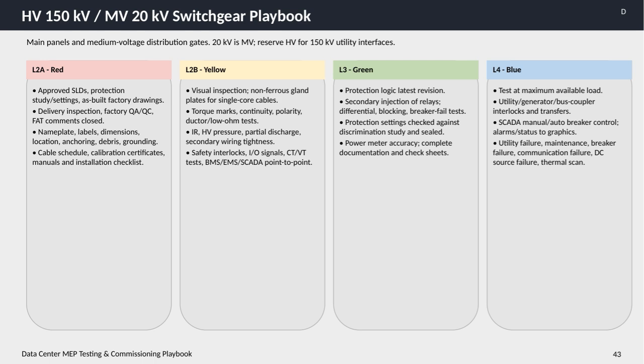This focuses on detailed visual and electrical inspections. Visual checks include confirming non-ferrous gland plates for single-core cables and torque mark verification. Electrical tests involve continuity, polarity, low resistance checks, insulation resistance, high voltage pressure tests, partial discharge measurements, and ensuring all secondary wiring is tight. Safety interlocks, input-output signals, CT/VT testing, and integration with automation systems like BMS, EMS, and SCADA are also validated point-to-point. In L3 marked green, the emphasis shifts toward protection logic and relay testing.